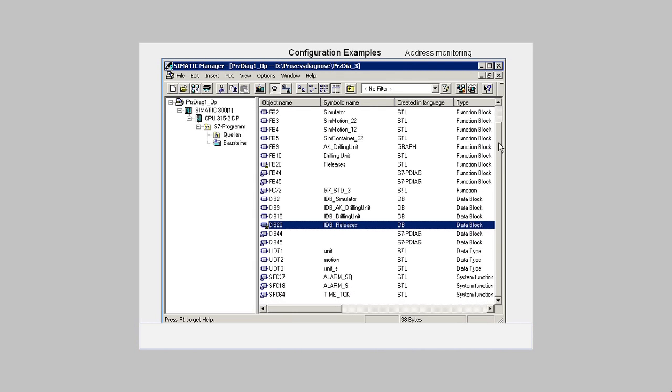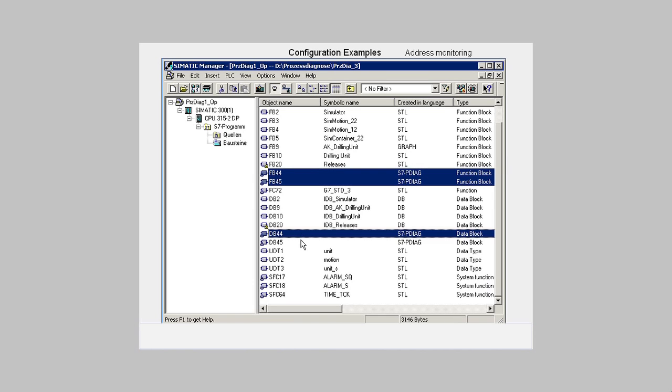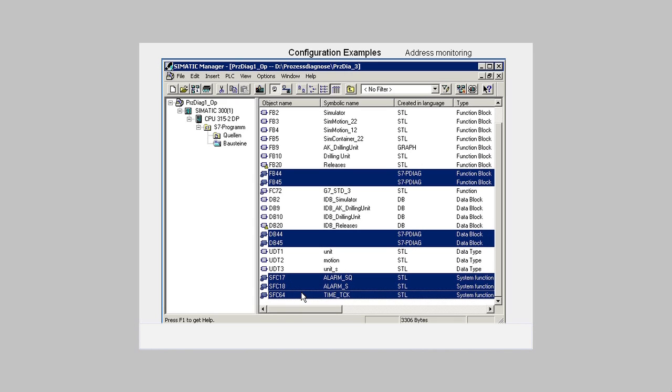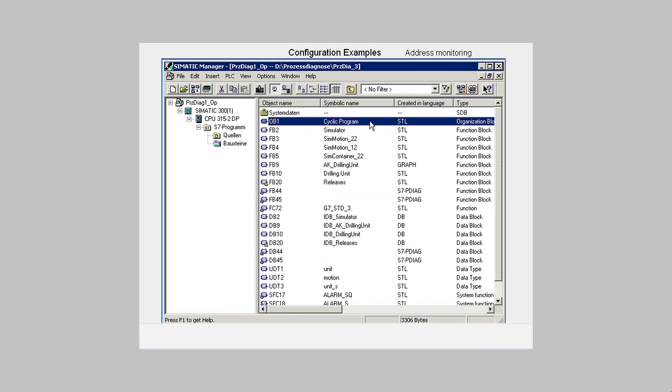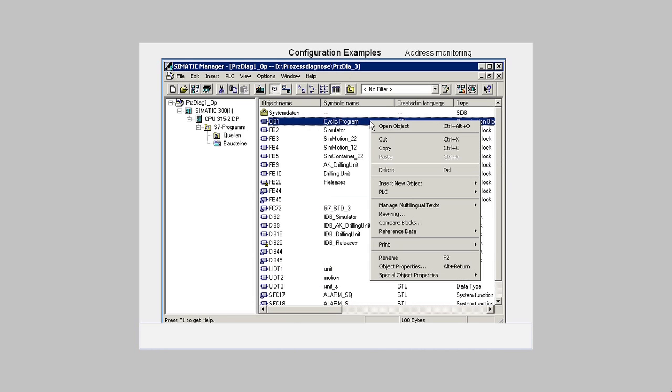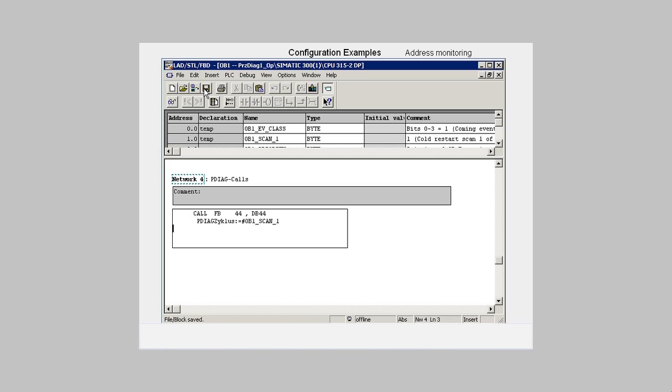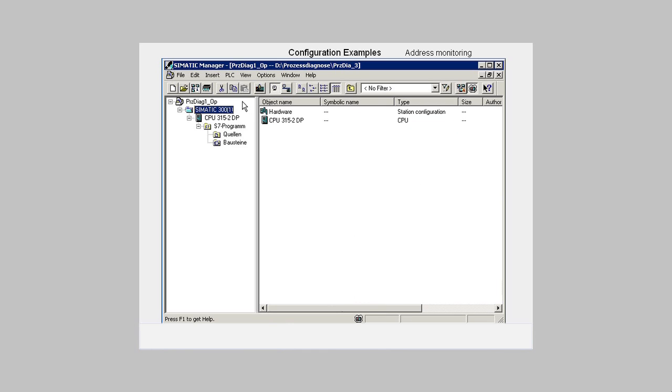In the block overview of the SIMATIC manager, we see the newly generated monitoring blocks and the required system functions. Then we open the OB1 and insert the code lines for calling the monitoring blocks. We save OB1 and close the block editor. Now we load the Step 7 project into the CPU.